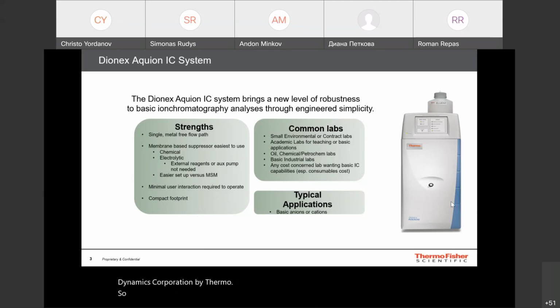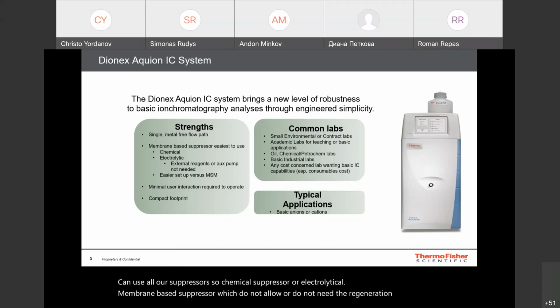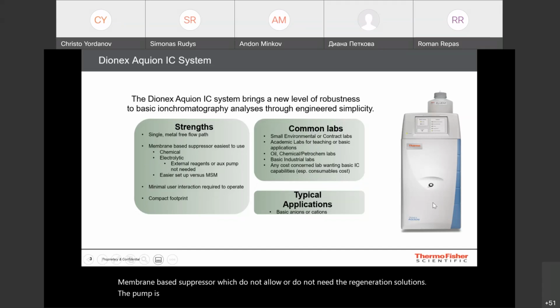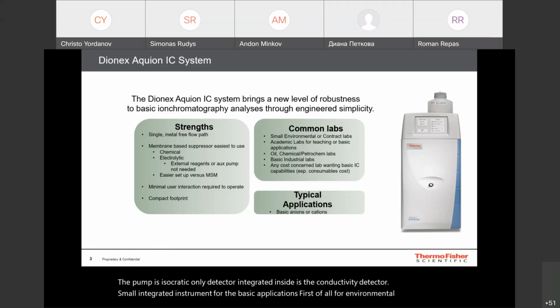The first system is called Aquion, an integrated system used for routine applications for basic anions or basic cations. You can use all our suppressors, chemical suppressors or electrolytic membrane-based suppressors which do not need regeneration solutions. The pump is isocratic only. The detector integrated inside is the conductivity detector. It is a small integrated instrument for basic applications, first of all for environmental laboratories, contract labs, and small academic laboratories for teaching purposes.